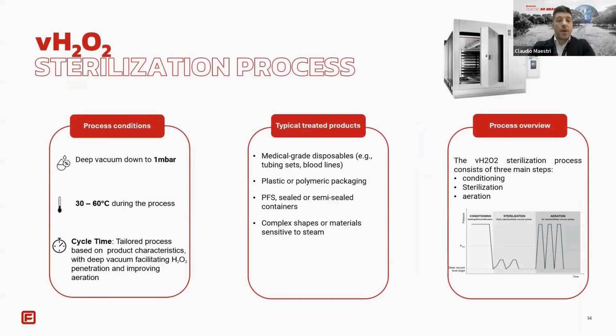So, starting from this evaluation, we develop an H2O2 sterilization process with the following process conditions. We work with a deep vacuum down to 1 millibar, with a process temperature between 30 and 60 degrees. The tailored process is based on the product features, with deep vacuum facilitating the H2O2 penetration and also the removal, the aeration as well. Some typical treated products are medical grade disposables like tubing sets, blood lines, plastic or polymeric packaging, pre-filled syringes, sealed or semi-sealed containers, and complex shapes or materials sensitive to the steam.